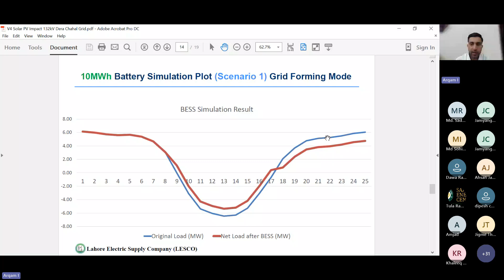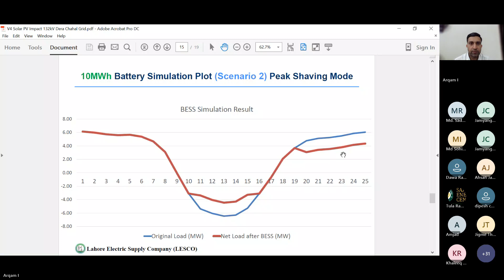Similarly, when we have peak shaving mode enabled for this battery energy storage system, it will only store energy once the power flow starts dipping below zero into reverse. It will shave this peak and store all the energy in this area into the storage available at the substation, and then the same can be supplied back from the evening hours, from 7 p.m. till 12 midnight. So hereby we will have this revised peak curve.